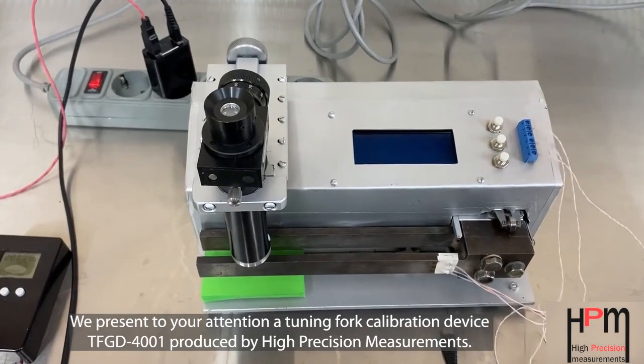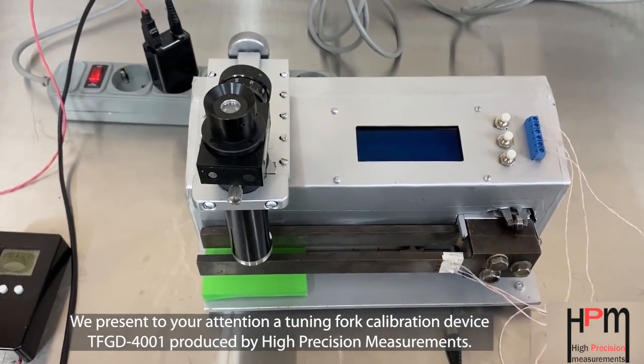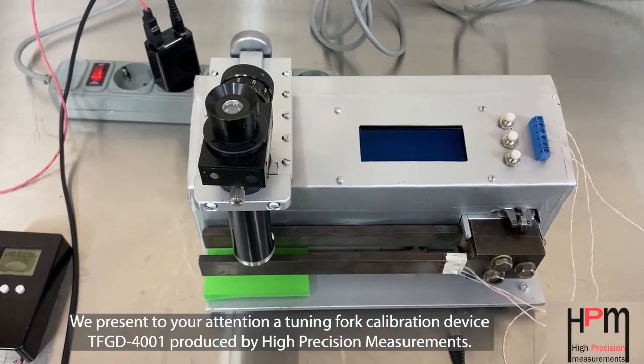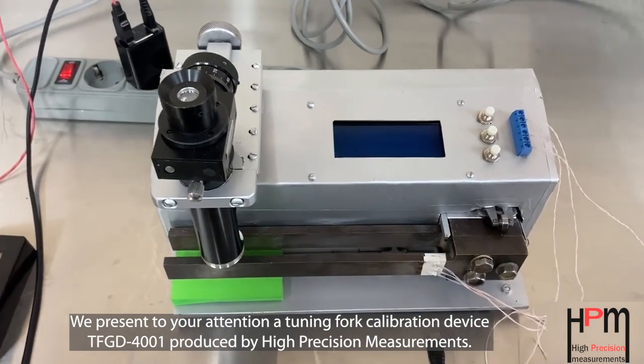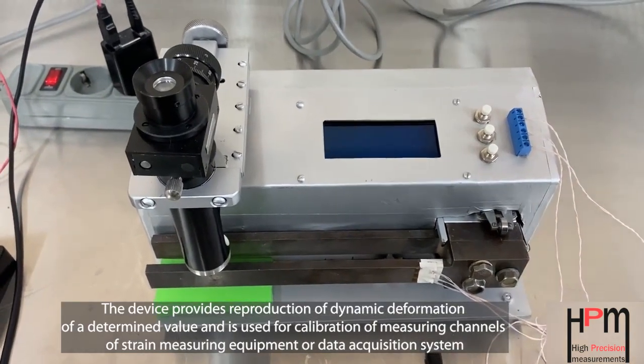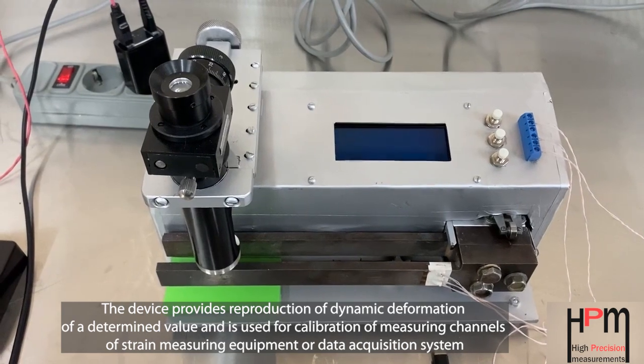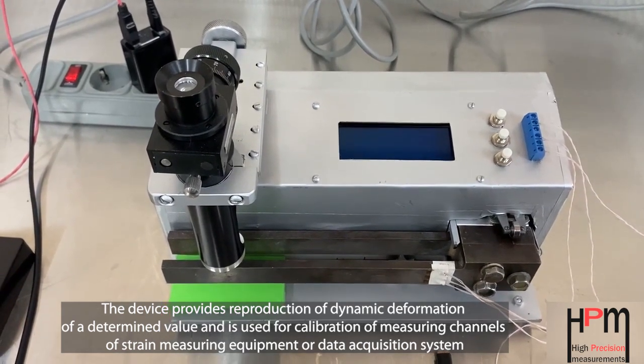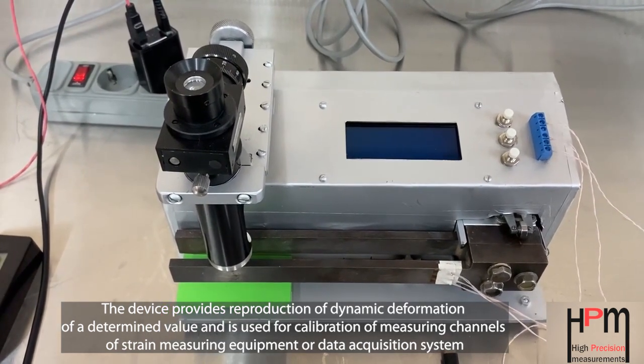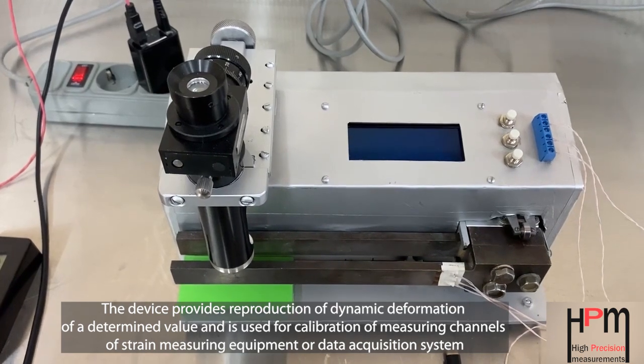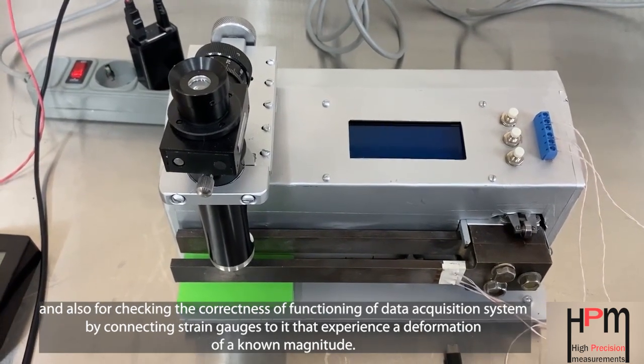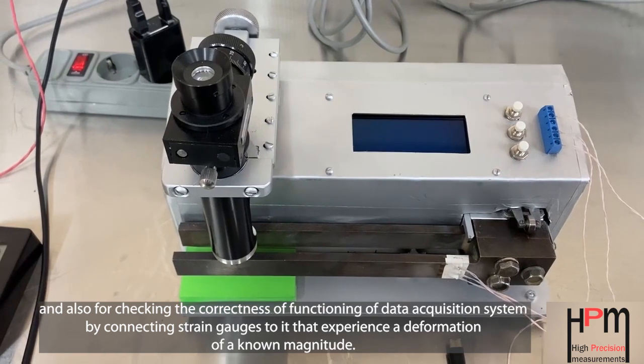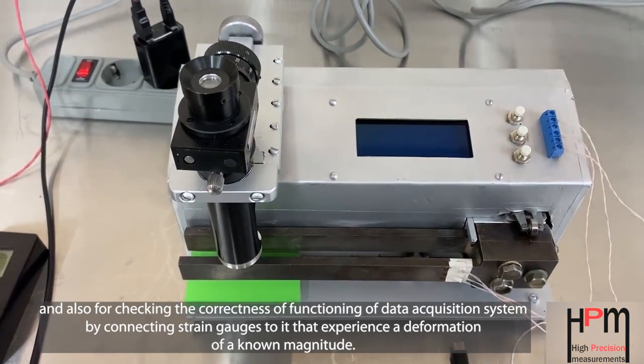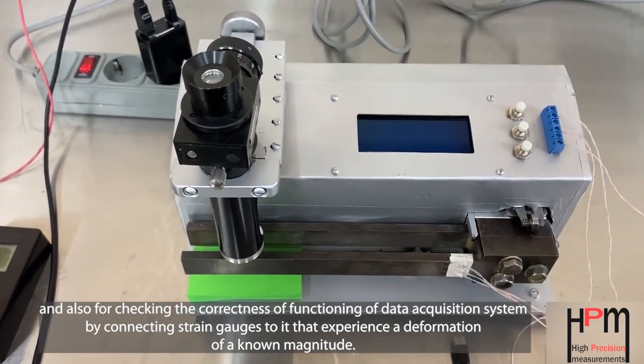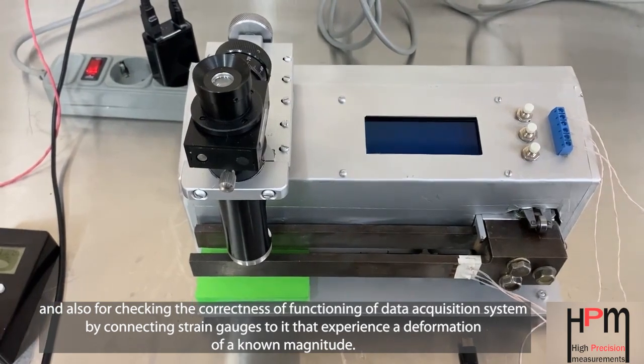We present to your attention a tuning fork calibration device, TFGD-4001, produced by High Precision Measurements. The device provides reproduction of dynamic deformation of a determined value and is used for calibration of measuring channels of strain, measuring equipment or data acquisition system, and also for checking the correctness of functioning of data acquisition system by connecting strain gauges to it that experience a deformation of a known magnitude.